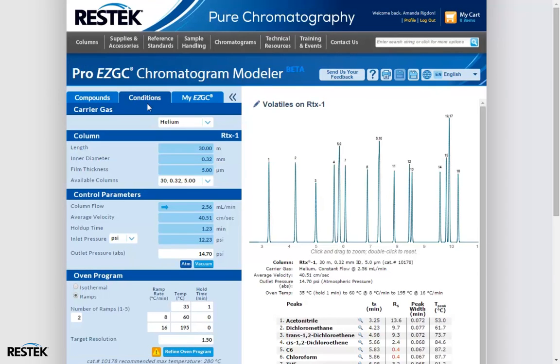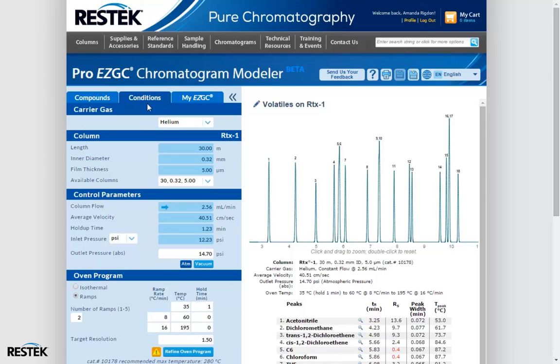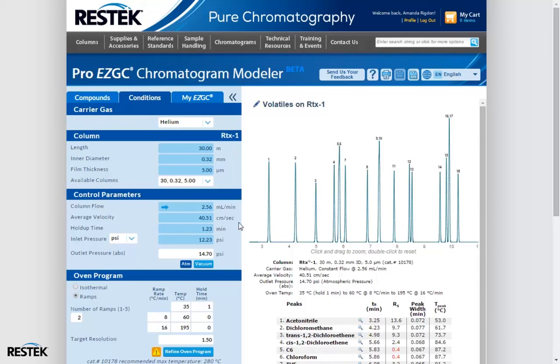The second portion of the interface pane is the conditions tab. This is where all the optimization is performed, so it's really the heart of the Pro EZGC chromatogram modeler. We've already discussed the layout of the conditions tab in video one, so I'll just point out that the parameters here are exactly the same as the parameters you'll be setting in your GC software, minus any inlet or detector parameters.